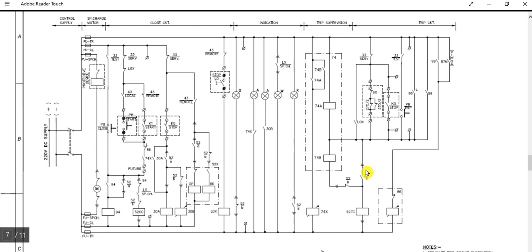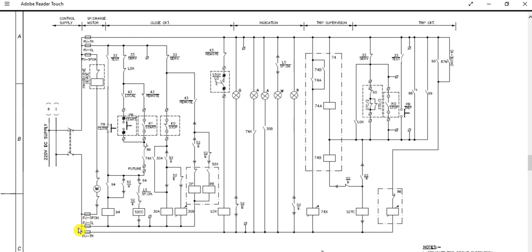Today I will cover the control circuit schematic for the motor feeder. This is an 11kV motor feeder control schematic drawing. The control supply is 220 volt DC — the positive bus is at the top and the negative bus is below.